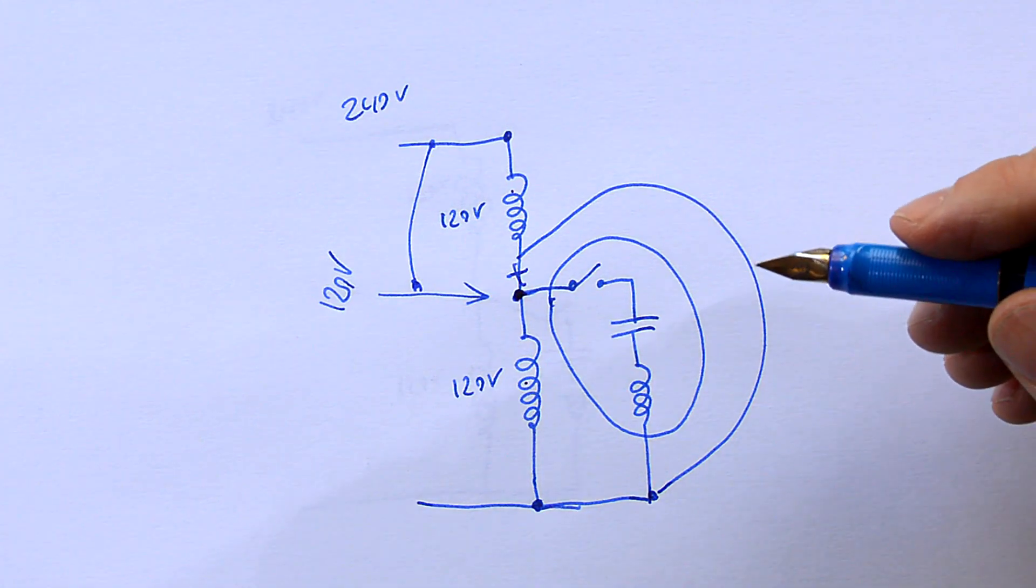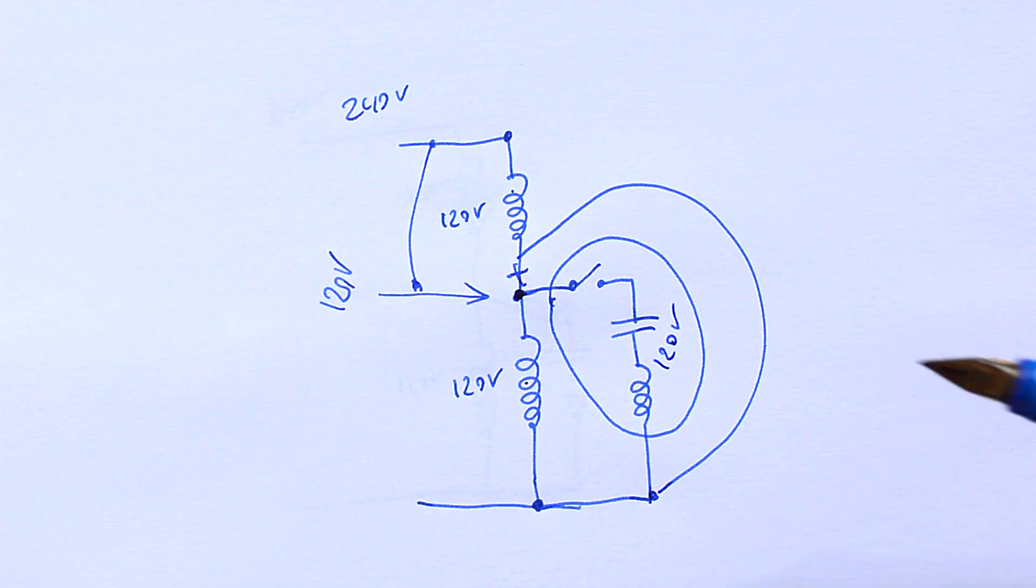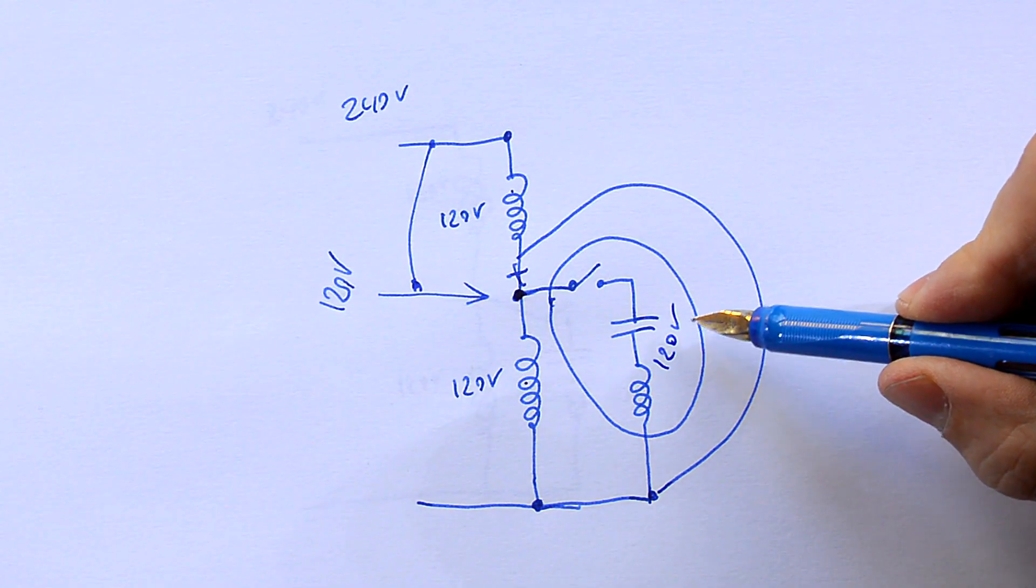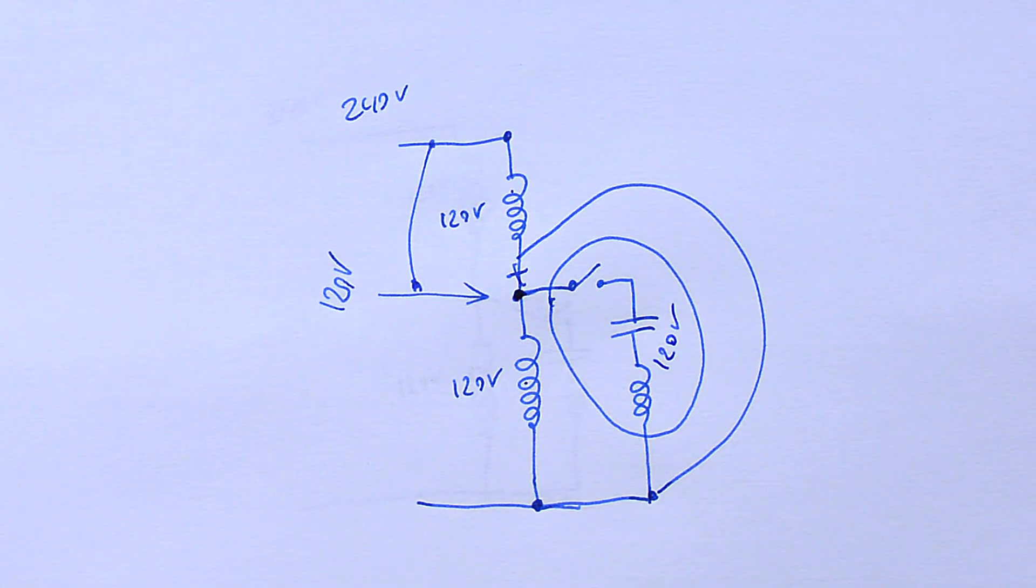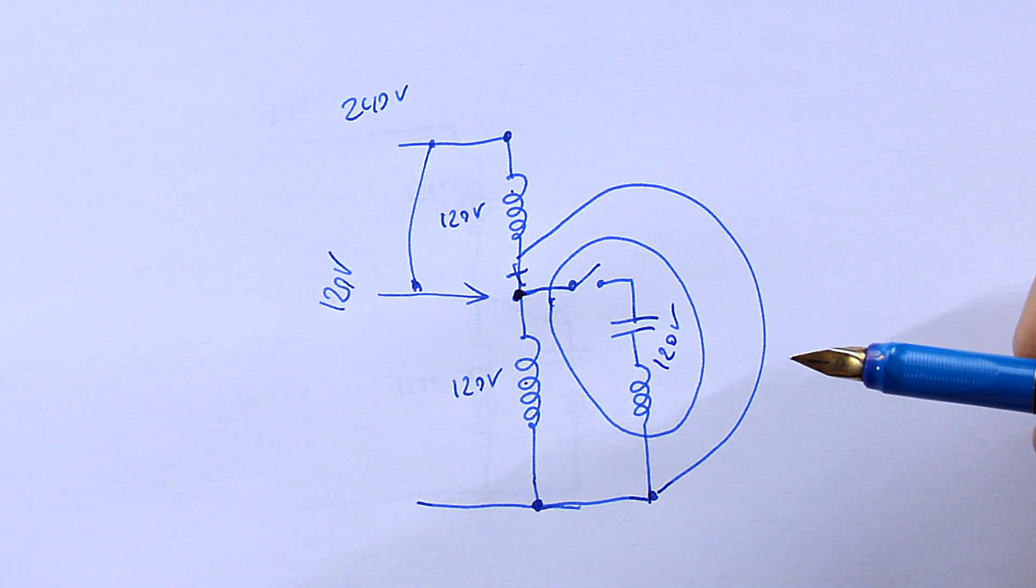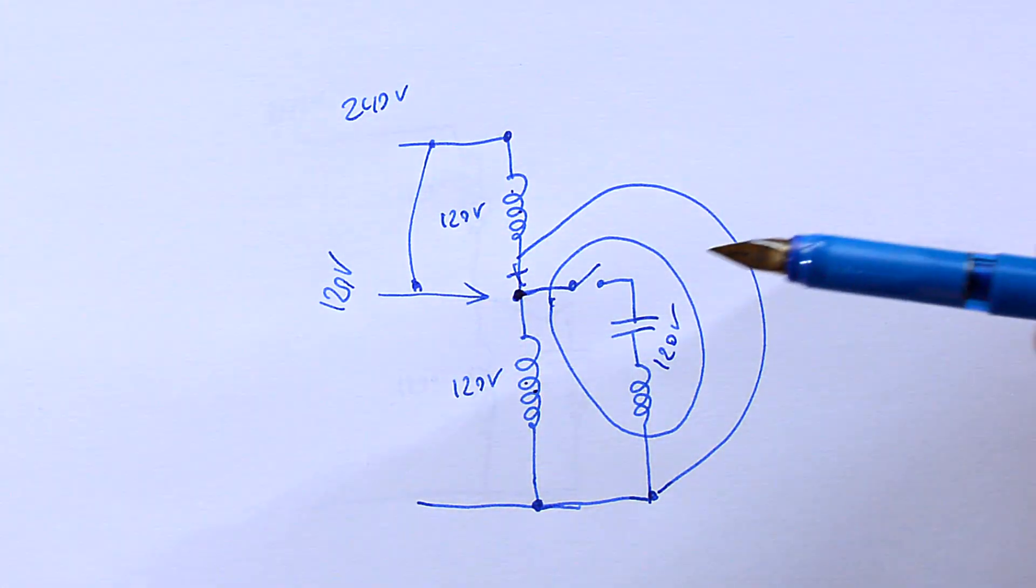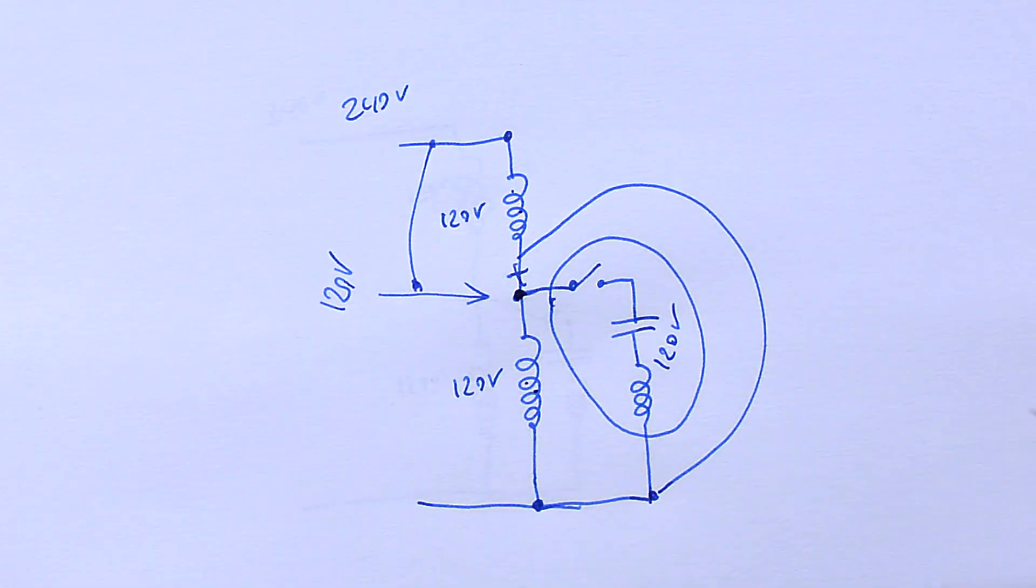And why does it work this way? Well this starter circuit here is a 120 volt circuit. And the reason it's 120 volts is if we're running the motor at 120 volts we don't have any more available than that. But if we're running the motor at 240 volts it's using these two coils inside the motor actually as an auto transformer to make the 120 volts from the 240 volts.